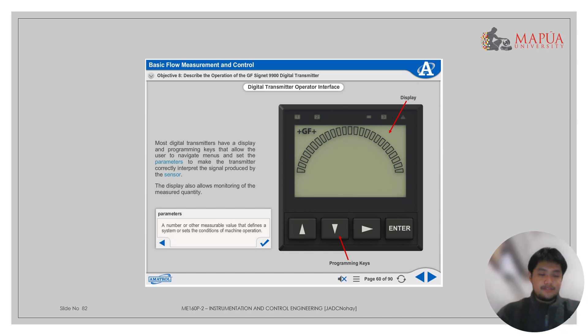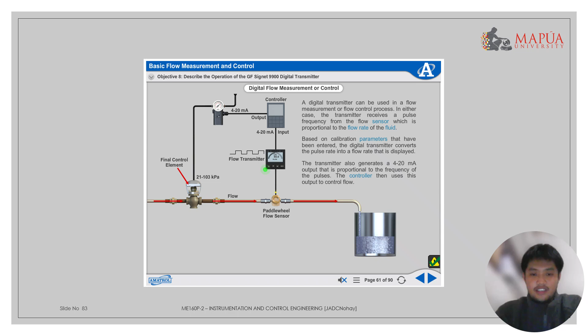Digital flow measurement or control. A digital transmitter can be used in a flow measurement or flow control process. In either case, the transmitter receives a pulse frequency from the flow sensor, which is proportional to the flow rate of the liquid. Based on calibration parameters that have been entered, the digital transmitter converts the pulse rate into a flow rate that is displayed. The transmitter also generates a 4 to 20 milliamp output that is proportional to the frequency of the pulses. The controller then uses this output to control flow.